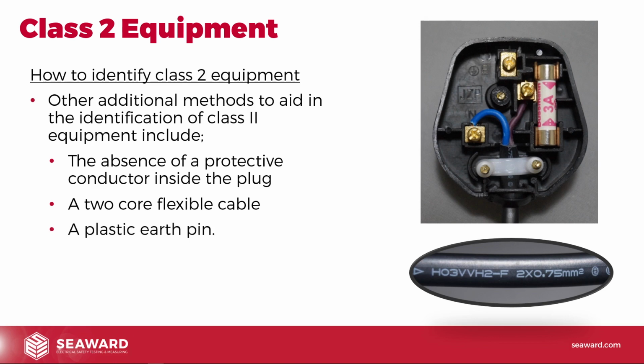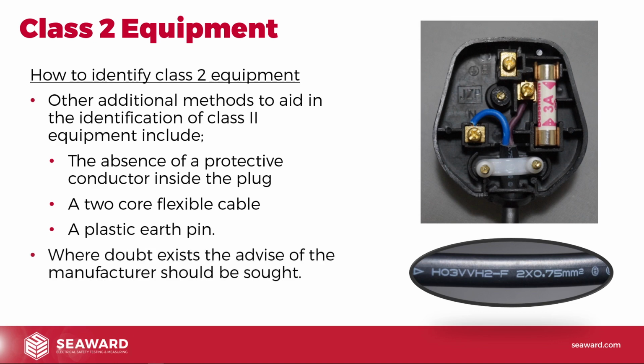Plastic earth pin. Again, I did mention that if you do see a plastic earth pin, generally that means that it is class 2 equipment, because class 1 equipment will always have a metal or a conductive earth pin. It won't have a plastic earth pin. So again, where any doubt exists, the advice of the manufacturer should be sought. So always err on the side of caution. If you don't know, always check with somebody who does from that side of things. It's never a problem to stop testing and say, look, I don't know, I need to do some more investigation.